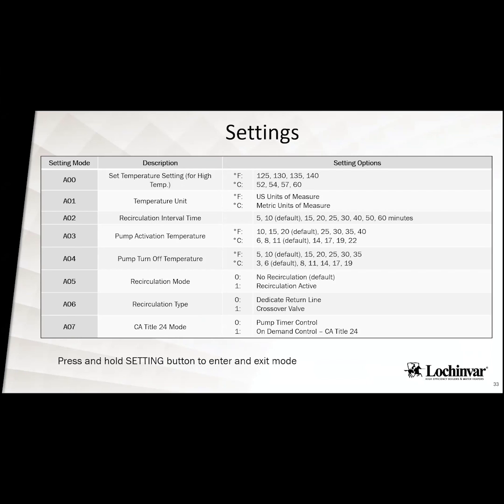So if you have it set for 120, it's going to recirc until it gets to 120, then it's going to shut off. And then once it drops 20 degrees, so once it hits 100 degrees in that thermistor on the incoming side of the unit, it'll kick that pump on again and recirculate till it gets back to 120 degrees. There's also the recirculation mode.